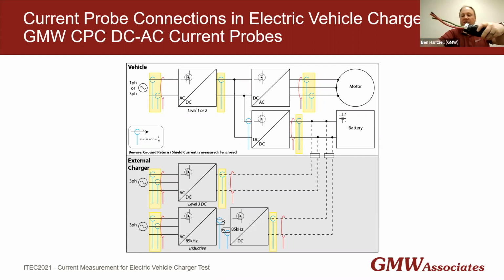which is actually some of the advantages you saw of the PEM Rogowski coil earlier. I can only do it with two hands, so I'm just going to slide it on. But you can imagine that this Rogowski coil was very easy to open and close around an individual conductor, very lightweight, easy to thread through in tight spaces. Very similar benefits to the CPC, except you're getting a DC-AC probe rather than an AC-only probe like the Rogowski coil.